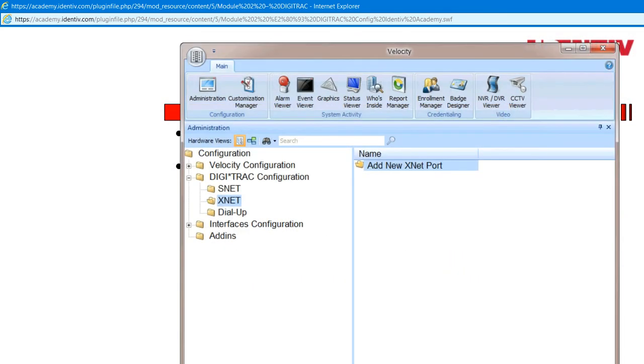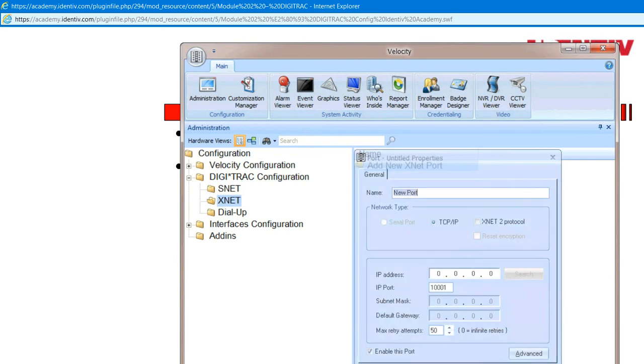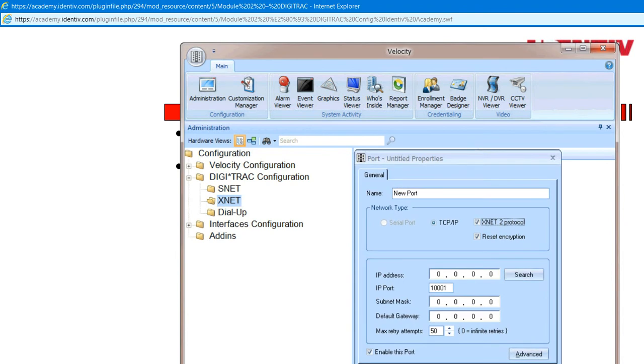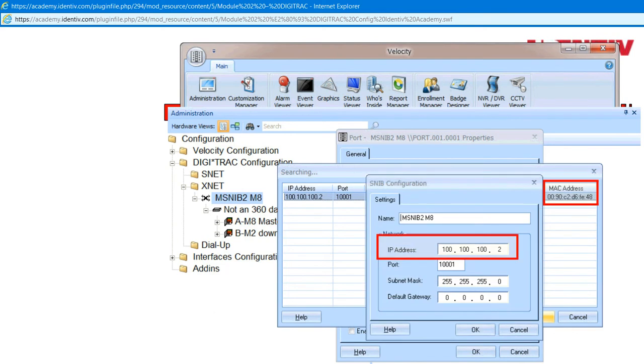SNV-2s connected to the network use standard Ethernet speeds. Now to add a port: expand DIGI*TRAC configuration, expand XNet and add a new XNet port. Select XNet-2 protocol — the only protocol for SNV-2s. Search for the SNIB2 by its MAC address. Double-click and assign a static IP address, a subnet, and a gateway if necessary. Notice that port 10001 is the default.